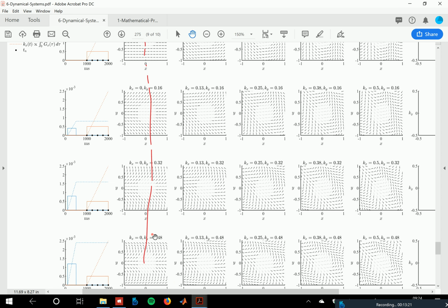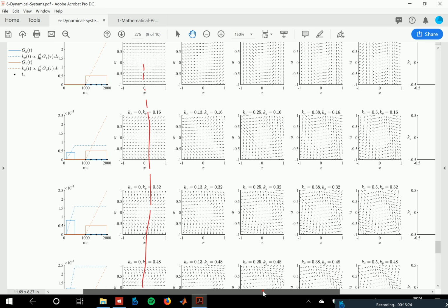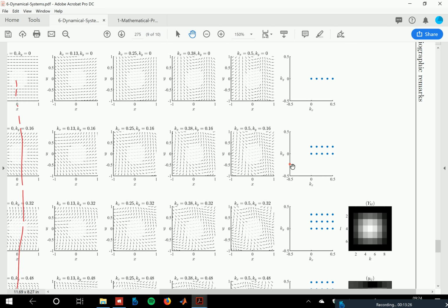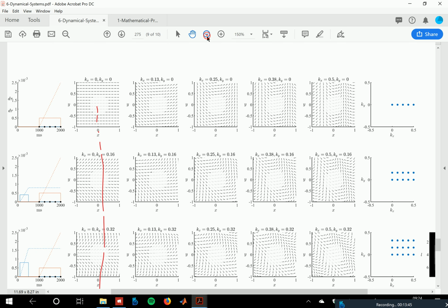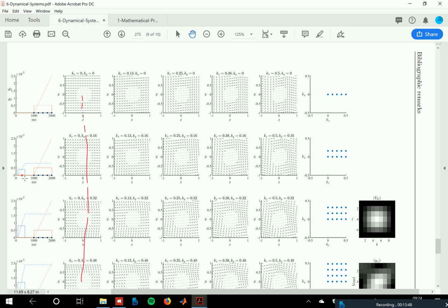Now, in terms of the k-space coordinates, we are still acquiring after each excitation 5 values of varying kx amplitude, so 0, 0.13, 0.25, 0.38, and 0.5. But if we start with a non-zero Y gradient here, and then increasingly higher Y gradients, we are changing the ky coordinate, and hence go to what is known as a higher line in k-space.